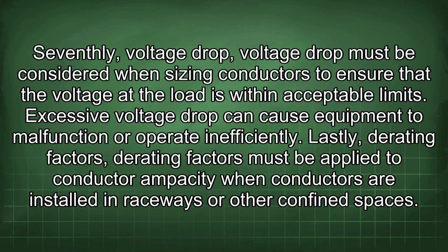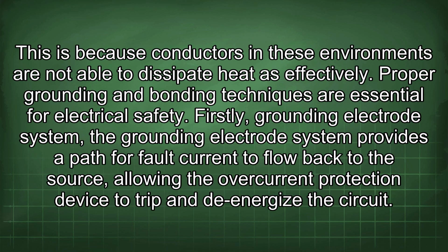Seventhly, voltage drop. Voltage drop must be considered when sizing conductors to ensure that the voltage at the load is within acceptable limits. Excessive voltage drop can cause equipment to malfunction or operate inefficiently. Lastly, derating factors. Derating factors must be applied to conductor ampacity when conductors are installed in raceways or other confined spaces. This is because conductors in these environments are not able to dissipate heat as effectively.